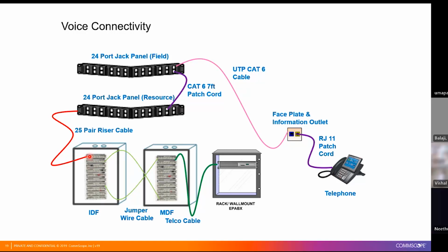Whatever riser cable you are bringing, you terminate at the rear end of the panel. It will be terminated on the 4 and 5 pins, with a Krone punch. And then with the RJ45, you can do the patching for all the voice connectivity. So the only additional components are the IDF and MDF, which are the same, and then you have the riser cable and the additional panels.